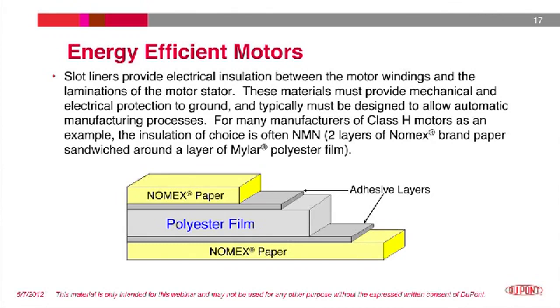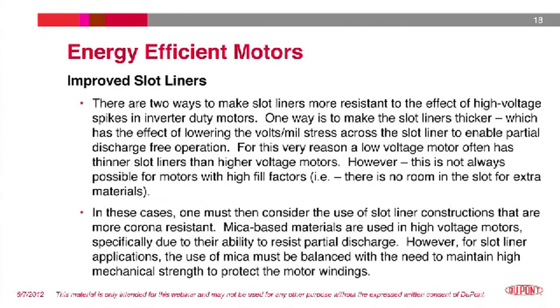Typically, this material is evaluated as part of an electrical insulation system, and for Class H motors, 180C, the insulation of choice is often NMN, two layers of Nomex paper sandwiched around a layer of polyester film, hence the name NMN. In this specific case, we decided to evaluate alternative slot liner materials to improve the overall life of the motors. There are two ways to make slot liners more resistant to the effect of the high voltage spikes in inverter duty motors. One way is to make the slot liners thicker, which has the effect of lowering the volts per mil stress across the slot liner to enable partial discharge-free operation.